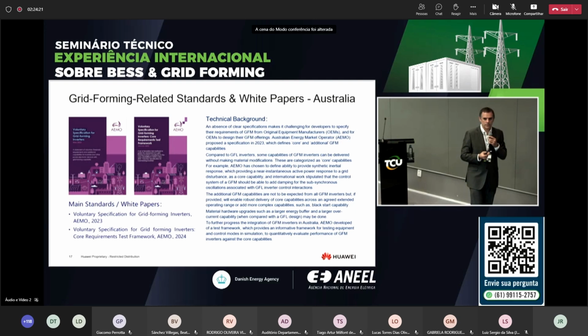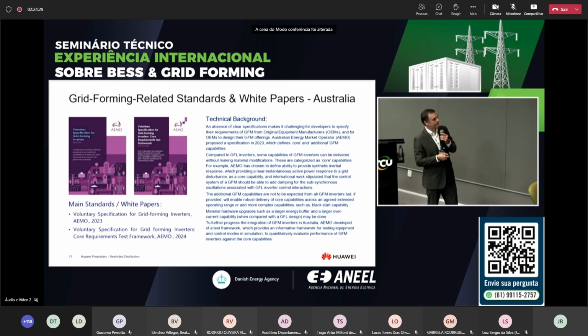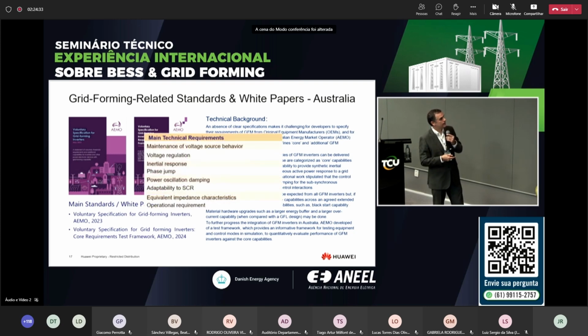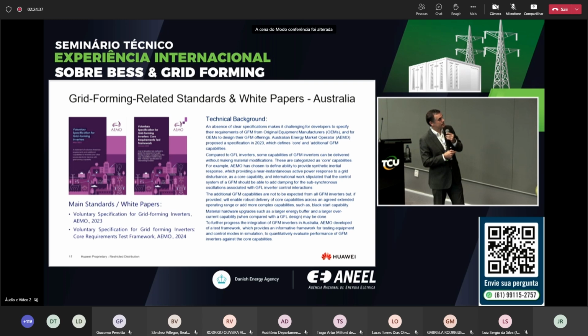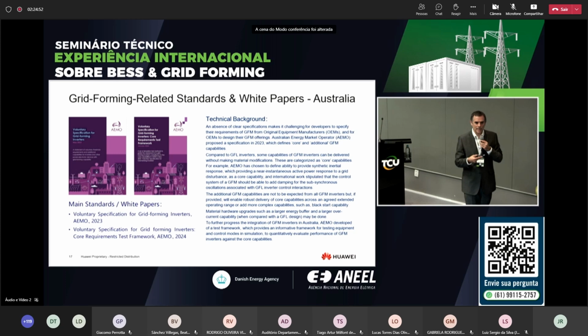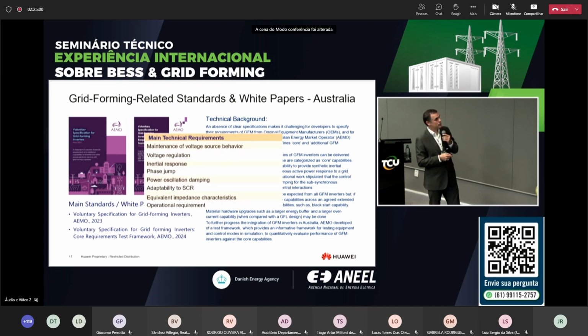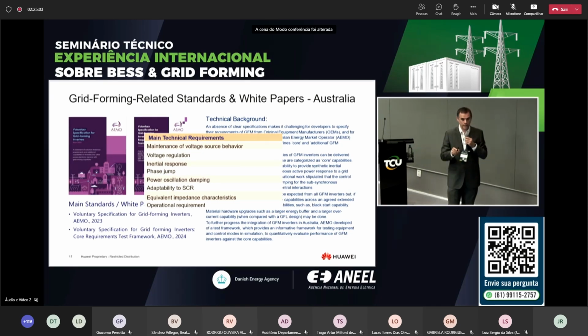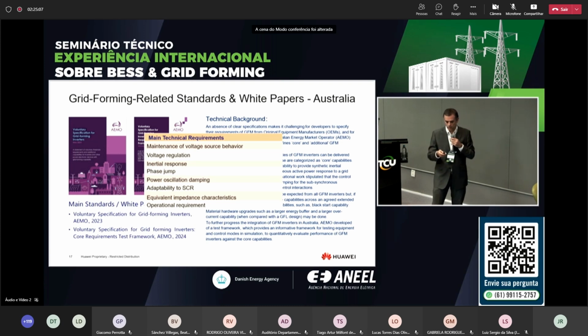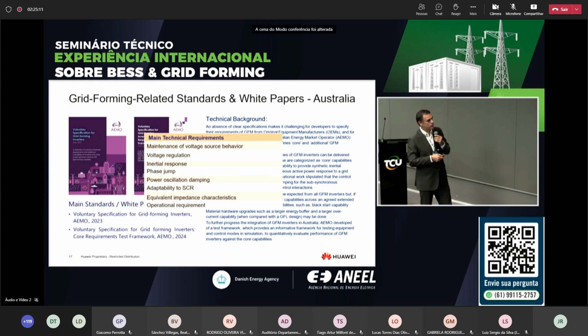In Australia, the main thing is what happens when the grid is very, very weak - the SCR will be very low, so the grid forming solution should keep working. This is voluntary specification for grid forming, but there is another document which is a requirement test framework, giving a guide about how to measure this grid forming solution. The main technical requirements are maintenance of voltage source behavior - again proving that it really works as a voltage source with impedance, like a synchronous generator - and adaptability to very low short-circuit ratio. What happens when there is no synchronous generator there?